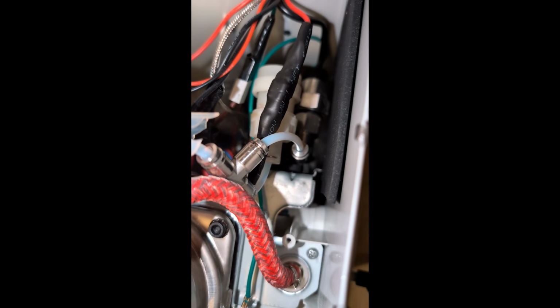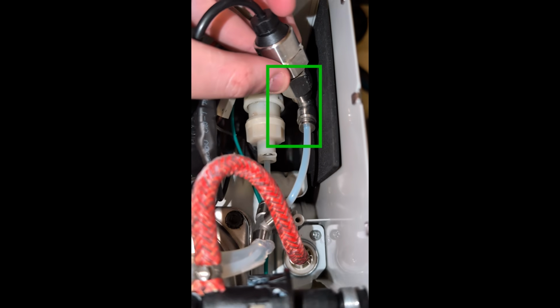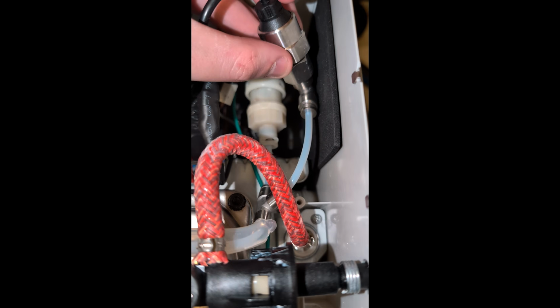In short, you need to cut the current tube cleanly with a sharp knife, about 1 to 2 inches from the pump. Insert a T-junction here. Then, attach a 4-inch tube on the remaining point of the T-junction. Attach the 90-degree pressure fitting at the other end. You should fill this tube with some water and then install the pressure transducer to this 4-inch cable.